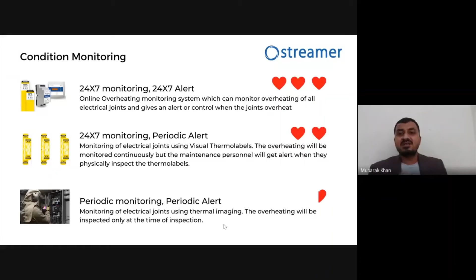Okay. So my personal best, I like 24/7 monitoring and 24/7 alert because it is 100% sure that it will save you 100% from the loose connection issues. Okay. Second priority is 24/7 monitoring and periodic alert. So if you don't have funds or it is very small or non-critical panel or some open areas, you can use the periodic alert. Okay. Thermal imaging, okay, it can also detect overheating, but not the electrical overheating which is causing damages of this scale.